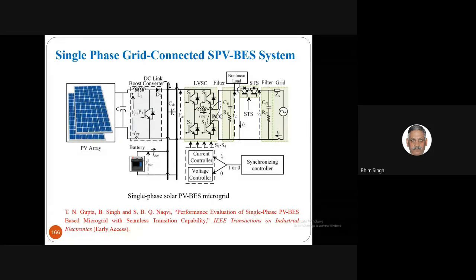Of course there are interesting challenges here: the many modes of control, and the synchronization to the grid. When the grid is not there, you have to operate the system in islanding mode with voltage control so that you get behavior like a UPS. Even looking into UPS literature, we couldn't find a very smooth transition; they talk about using a relay, but we can't operate the system that way, so we have to have a well-designed synchronization algorithm.